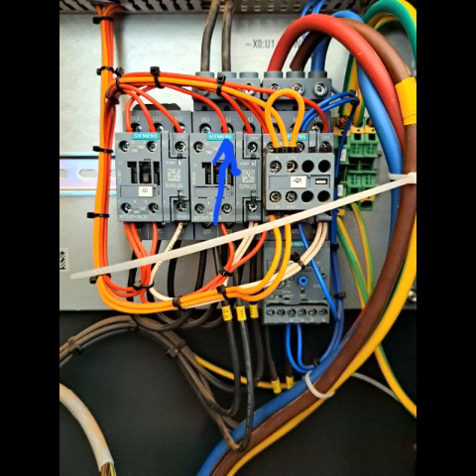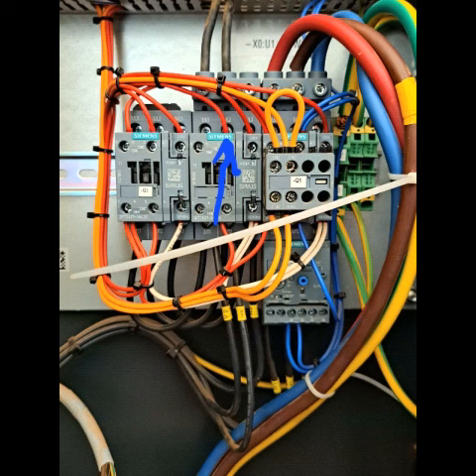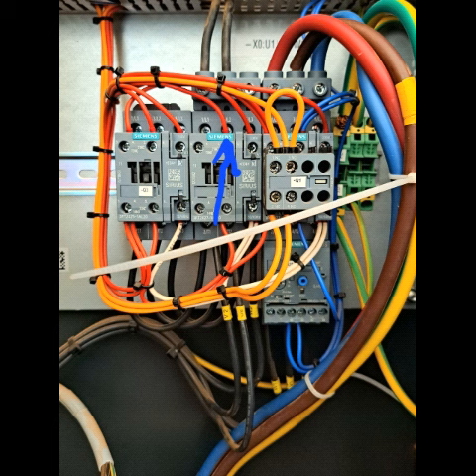On the middle contactor you can see a blue arrow pointing at the normally closed terminal which I found to be faulty and did not let the signal through to the controller. That's why this error came up over and over.